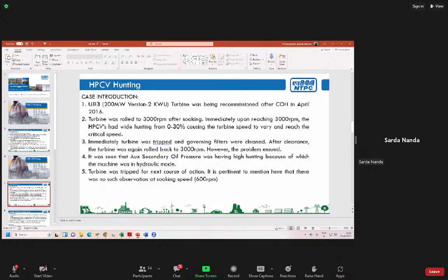on soaking speed. There was no problem. Then the turbine was rolled to 3000 RPM. Immediately upon reaching 3000 RPM, the HP control valves had wide variation. And that caused the turbine speed to vary and reach critical speeds. Immediately, we tripped the turbine. Governing filters were the first line of defense. We cleaned the governing filters, but still this problem persisted.